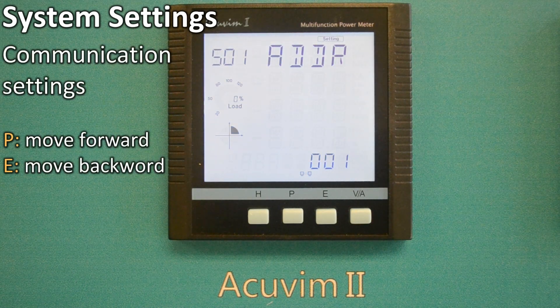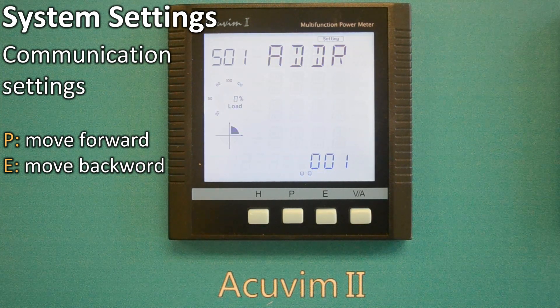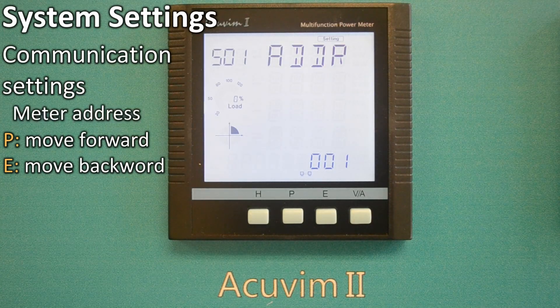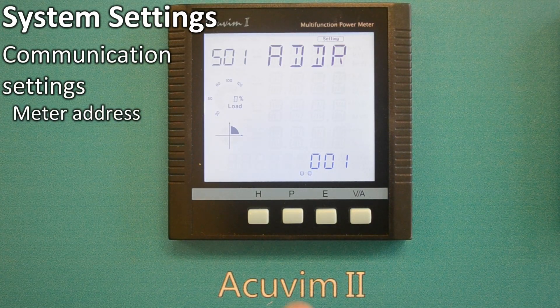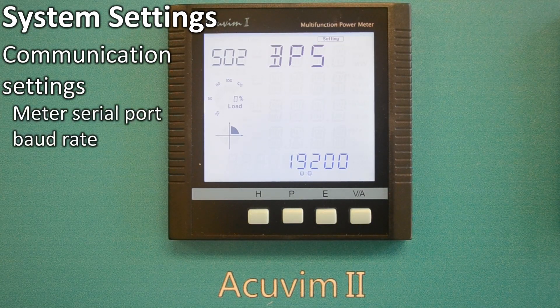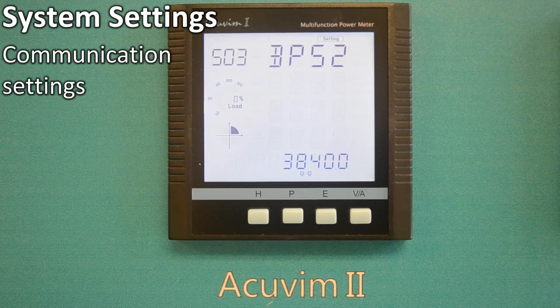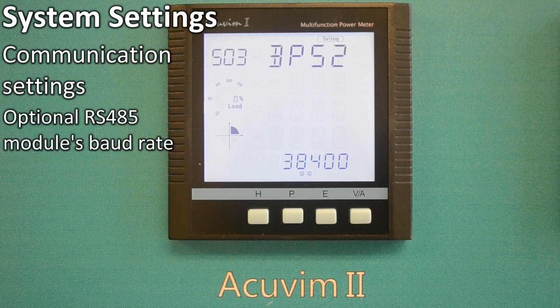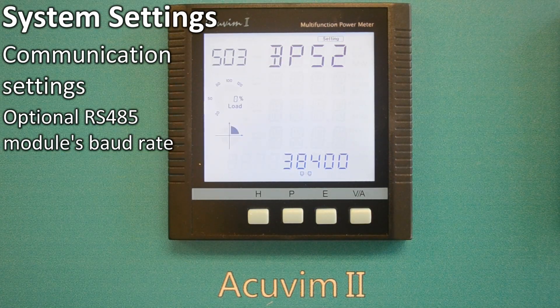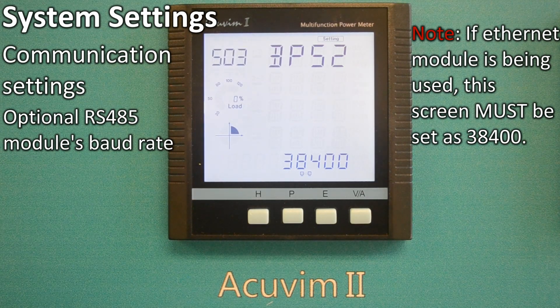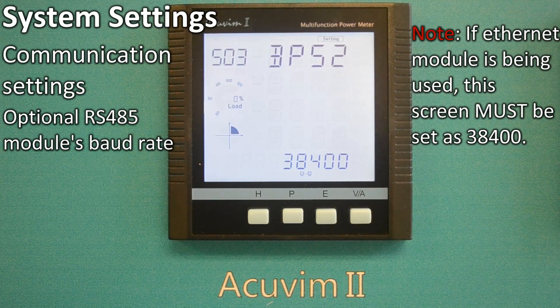Now let's look at the communication settings. Press the P key to move forward to the next screen, and the E key to move backward. The first screen is ADDR001, meaning the meter address is 1. The second screen shows BPS 19200, meaning the meter serial port baud rate is 19,200 BPS. The next one shows BPS 38400, meaning the optional RS-485 module's baud rate is 38,400 BPS. Please note, if you wish to use the Ethernet module, this screen must be set at 38,400. Otherwise, the Ethernet module will be inactive.